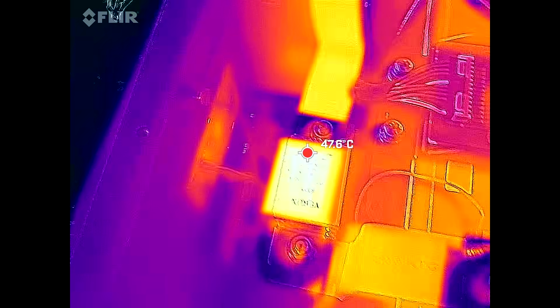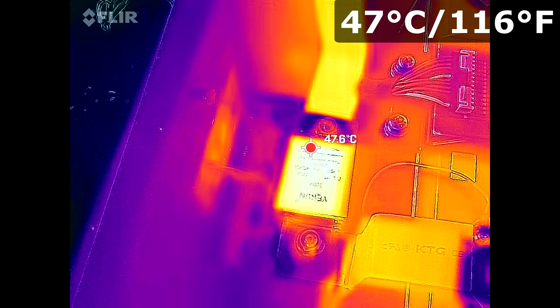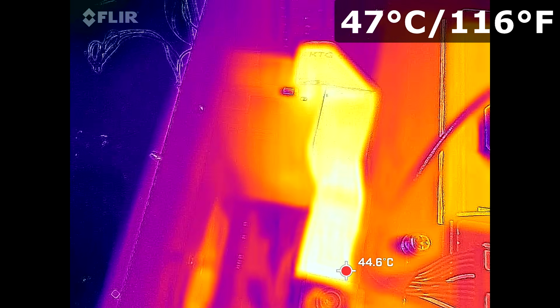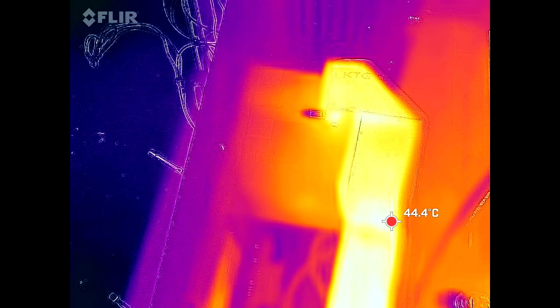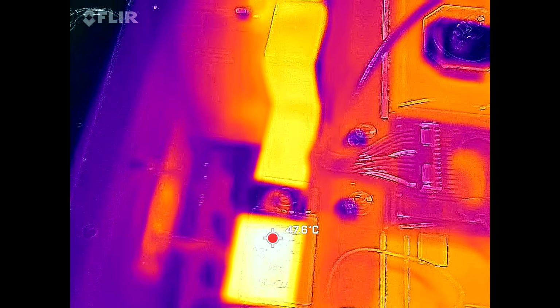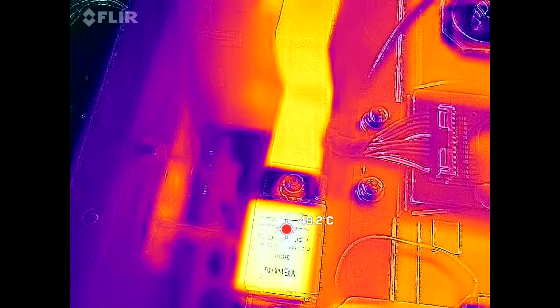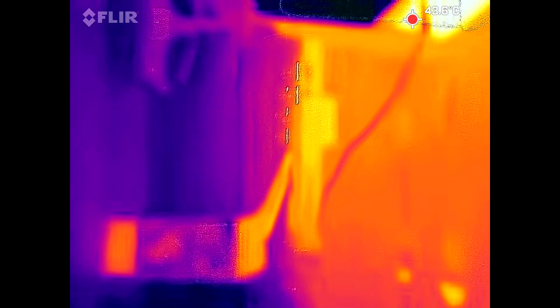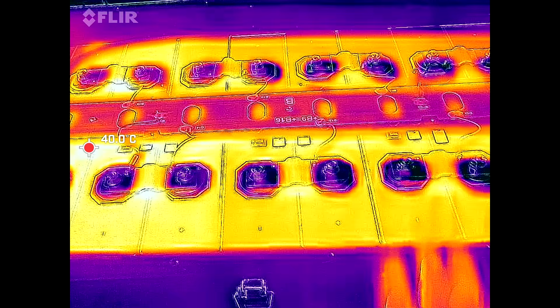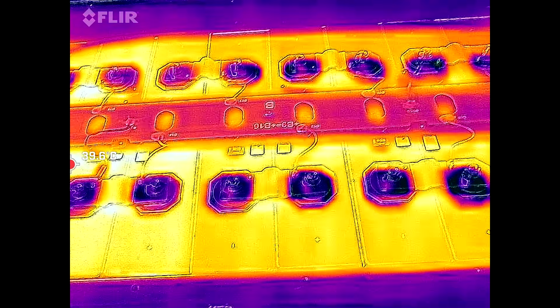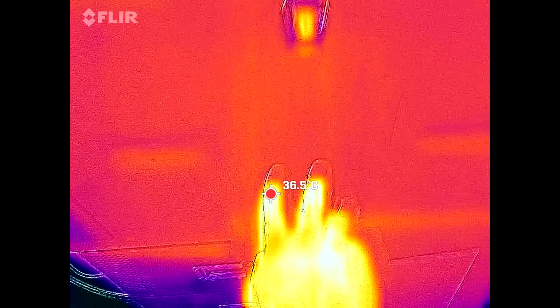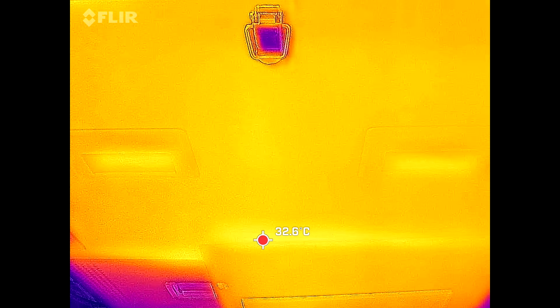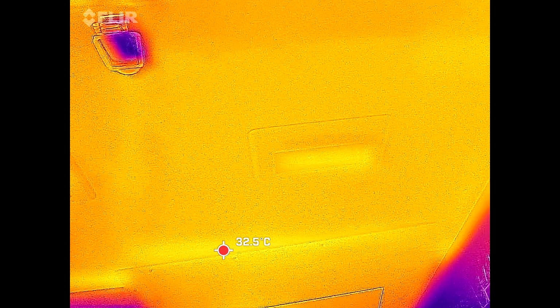So on here at the front, the fuse has cooled down a bit, around 47 degrees. So has the bus bar and the connection to the circuit breaker, because we already have reduced the current from 100 amps to 70 amps, so this makes already a difference down here. BMS itself, no issues down there. So at least we know the top layer of the batteries is totally fine, no hotspot, nothing. We don't know anything about the bottom layer in the battery. From the outside, it looks good.